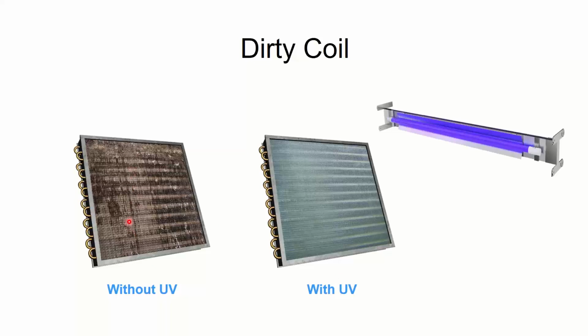If I took this dirty coil on the left and put a UV bulb on it, it would eventually look like the coil on the right. Now, I'm not going to do that because it's going to take months for that to happen. It's got to kill all the stuff on this. Then as that coil heats up and cools down, it'll expand and contract. The stuff will get brittle, it'll flake off, and I can kill the stuff under it and repeat that process.